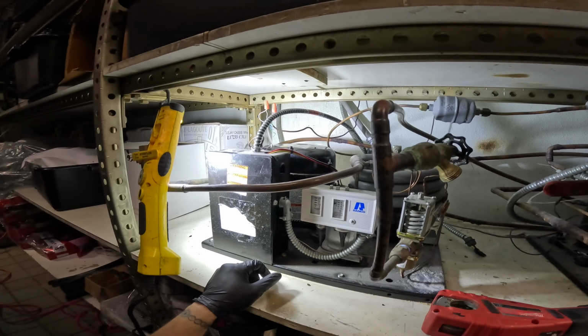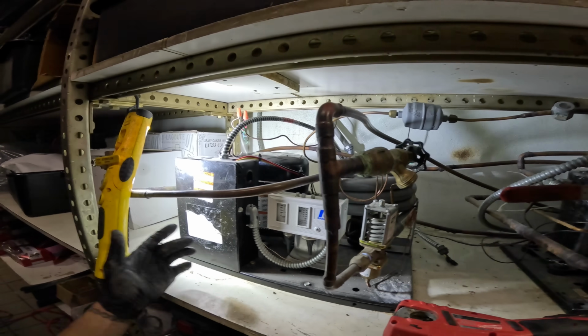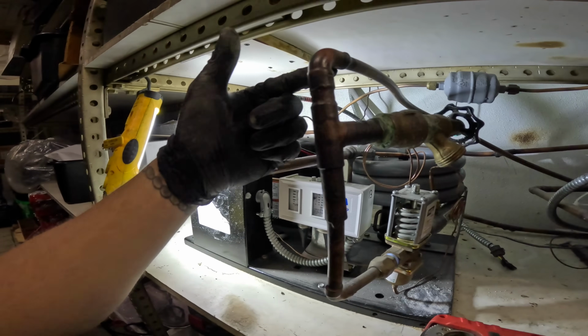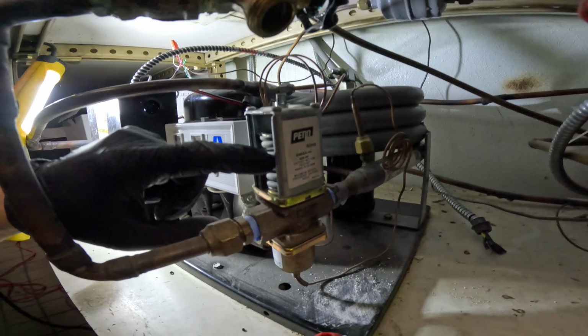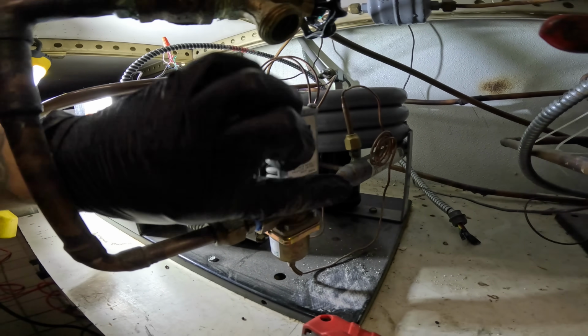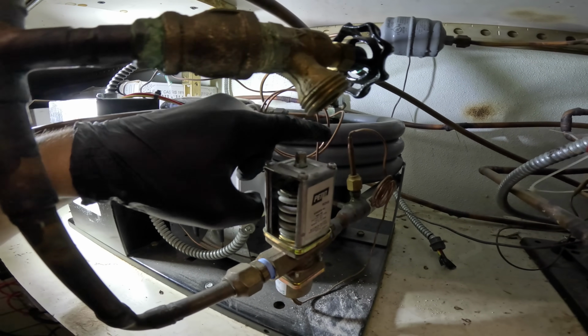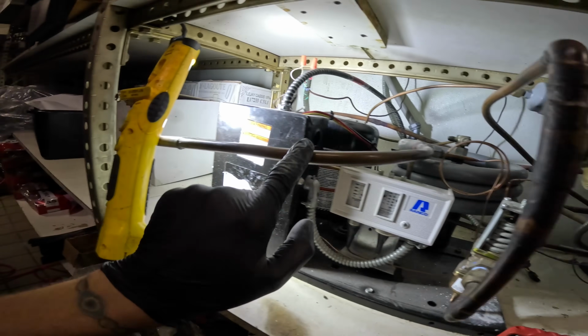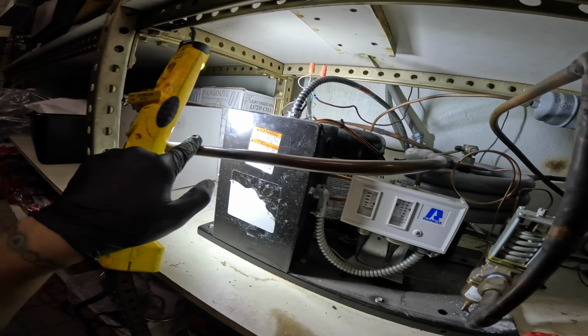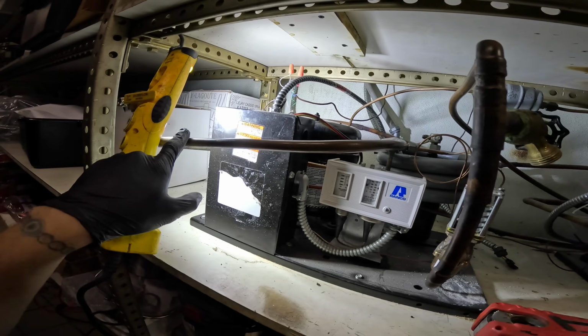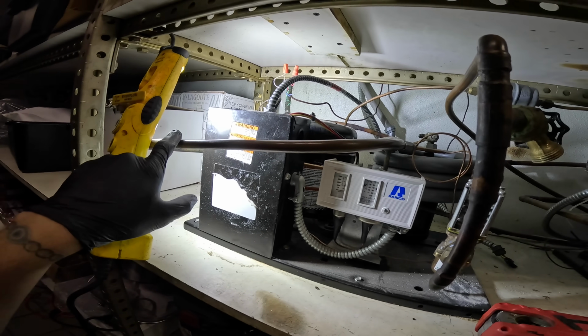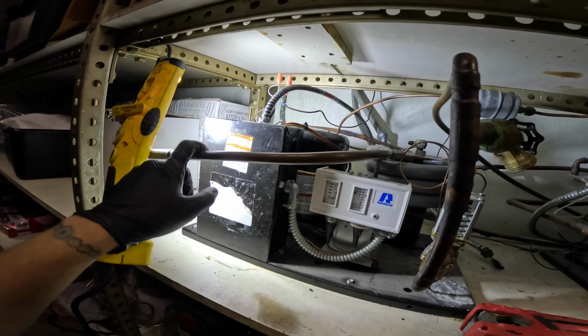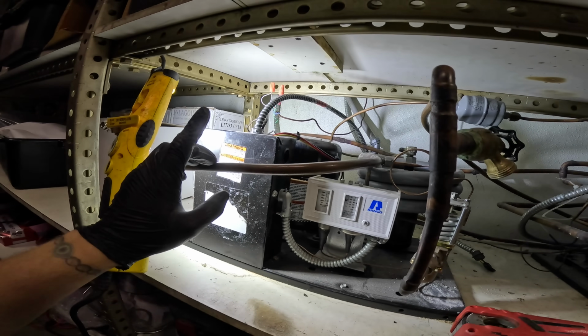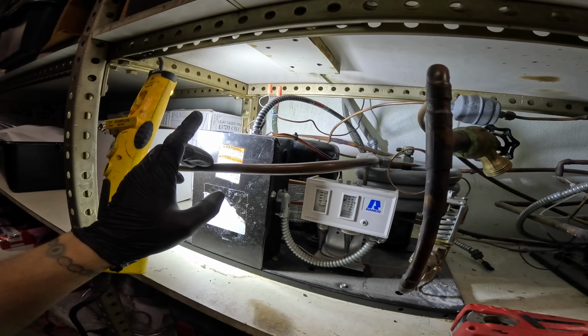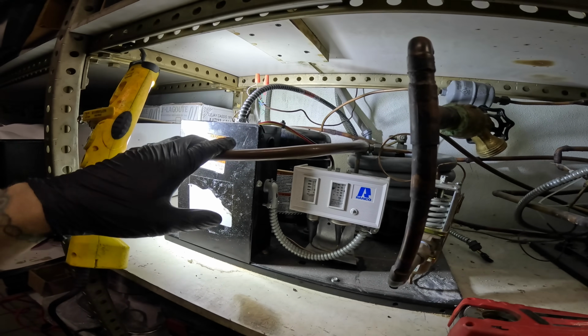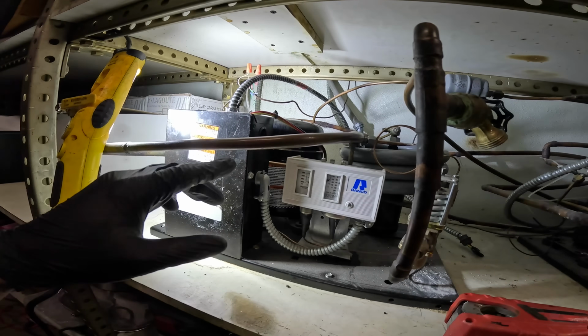Okay, so the water-cooled condensing unit has an inlet and an outlet. Water comes in through the water regulating valve and goes into the condenser, that's this coil right here, then out of the condenser coil. So supply and return gets pumped through centrifugal pumps throughout the building into a cooling tower. In the cooling tower it rejects the heat, then comes back cooler, and the cycle continues.